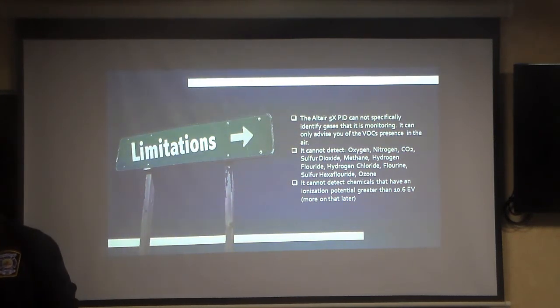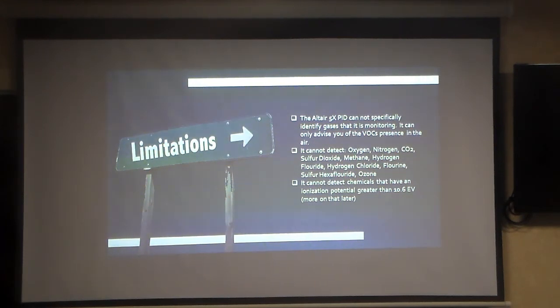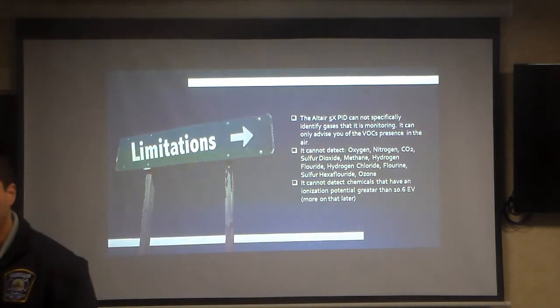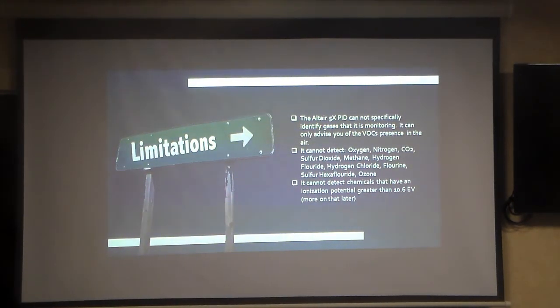So it's not going to detect oxygen the way the PID would. There's an oxygen sensor on here, it will detect oxygen, but the PID won't detect oxygen. Does that make sense? This is a visual. We have an oxygen sensor on here, it's just that the PID cannot detect oxygen. And of course, remember 10.6 - any gas of 10.6 or above, the PID cannot see.